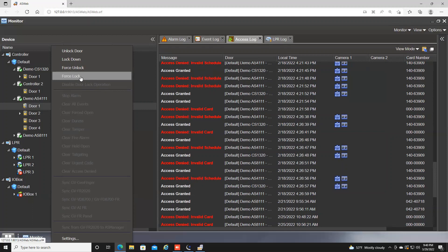The exact opposite is Force Lock. If your facility is scheduled to unlock at 8 a.m. and relock at 5 p.m., but you need to secure it, you can hit Force Lock to lock the door and override your existing schedule. Note that if you force lock the door, employees' or residents' access cards would still allow them to get through the door. Your last option is Lockdown — the highest level of secure lockdown. This locks the door and no credential can get through unless, when setting up their credential, you checked the box that gives them access to go through a door in a lockdown state.